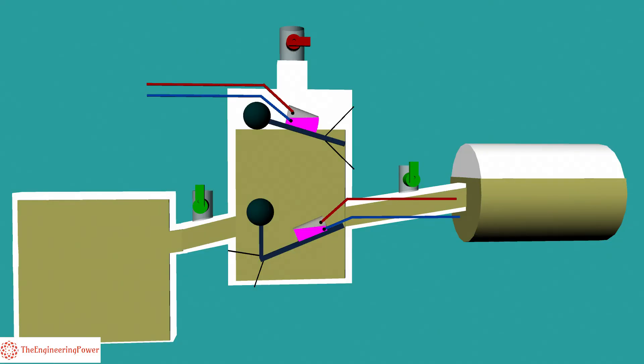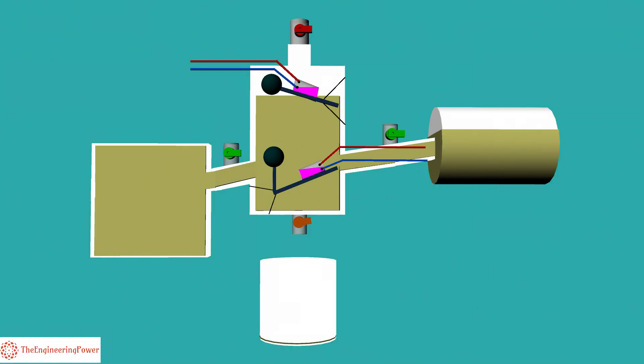For testing the operation of Buchholz relay for trip function, the following procedure is adopted. First, the valves to the Buchholz relay from both the main tank and conservator are closed so that during testing oil doesn't come to the relay. Then oil is drained from the Buchholz relay through the drain plug located at the bottom of the relay.